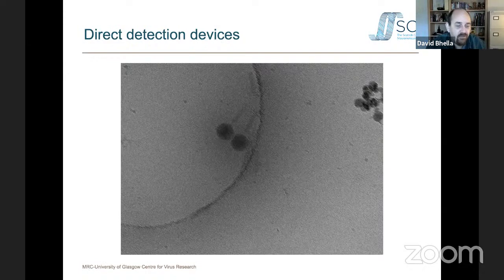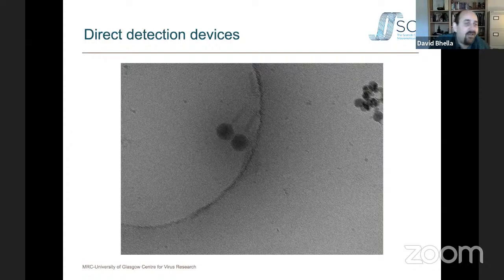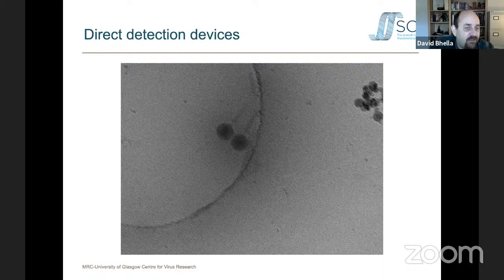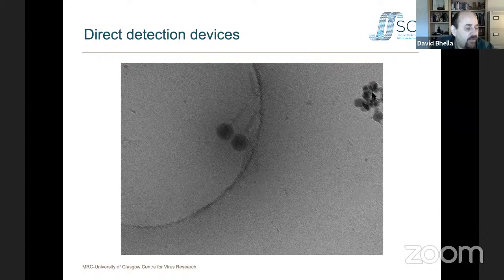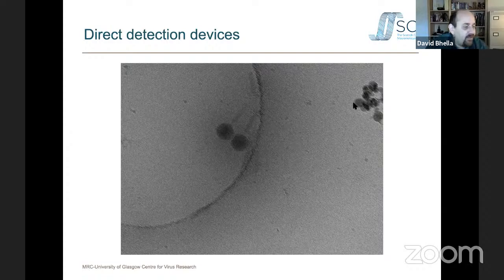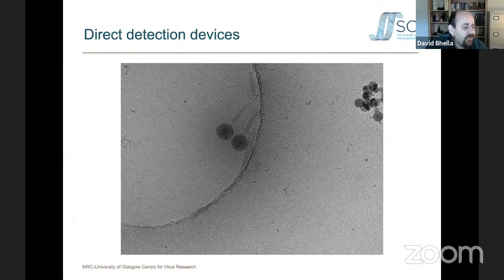These detectors needed to be radiation hardened and made thin enough so electrons don't bounce around causing signal blooming. The great advantage of CMOS direct detectors is massively parallel readout giving very fast performance, allowing recording of movies rather than single frames. On a CCD, a one-second exposure recorded as a single frame would be blurred if the object moved at all — a huge problem for many years. Now, rather than recording single frames, we record movies which can be aligned and integrated to produce a final micrograph, correcting motion and applying dose fractionation to exclude radiation damage.